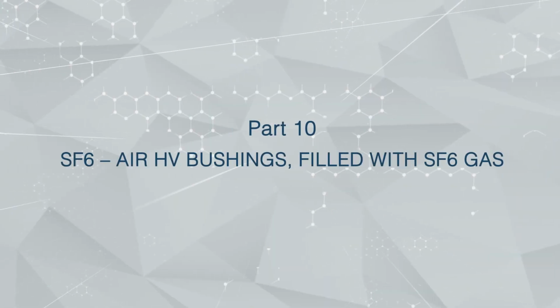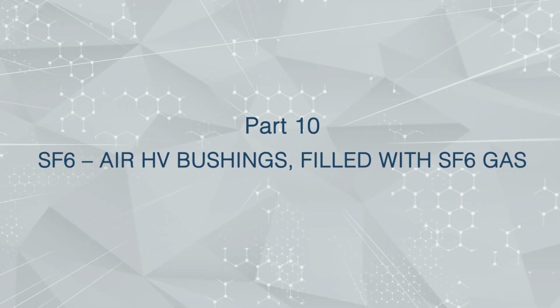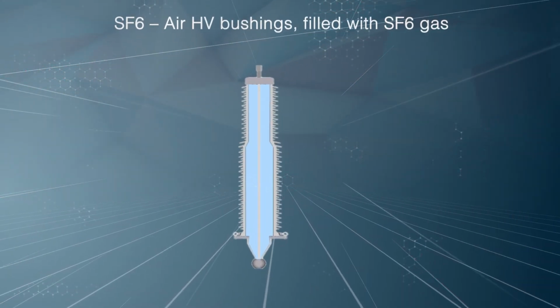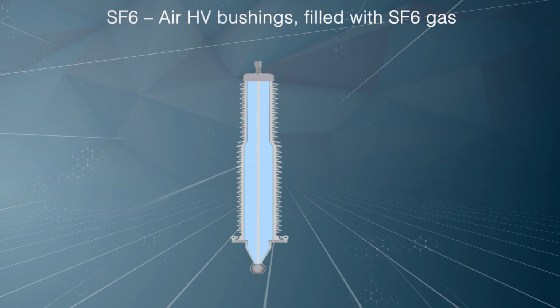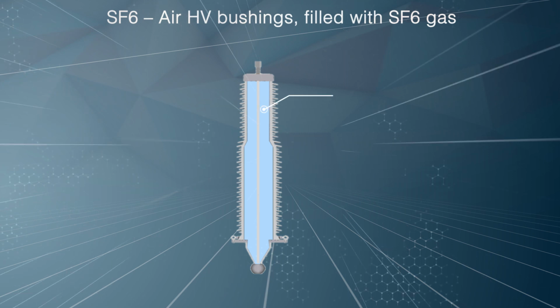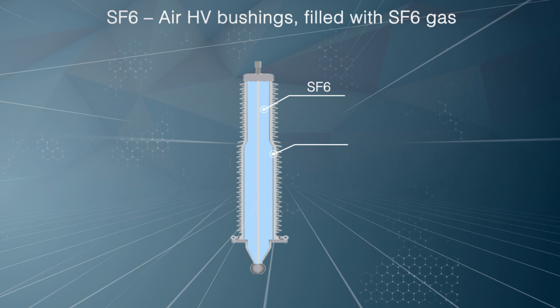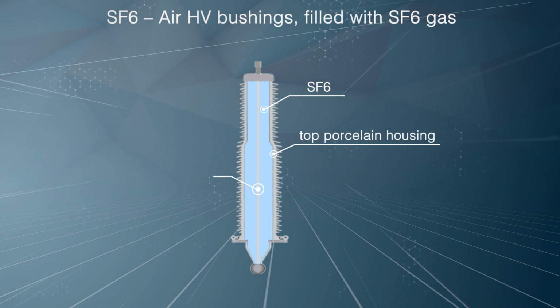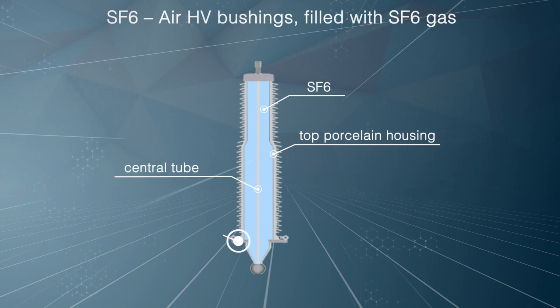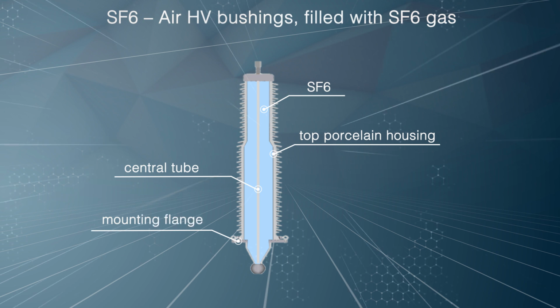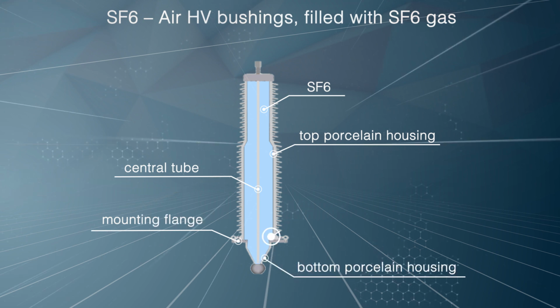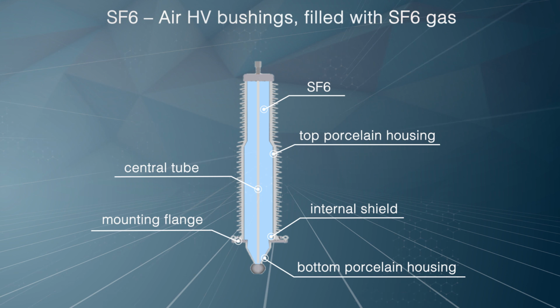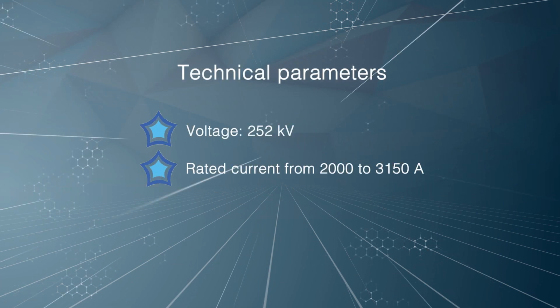This application area is also relevant for SF6 air HV bushings filled with SF6 gas. Their difference is in the simplicity of construction. No insulation core, no equalizing or condenser liners, no need in test tap. However, in order to create an enclosed volume, the bushing has a bottom porcelain housing. To equalize the electric field inside the bushing in the grounded flange area, they use an internal shield.